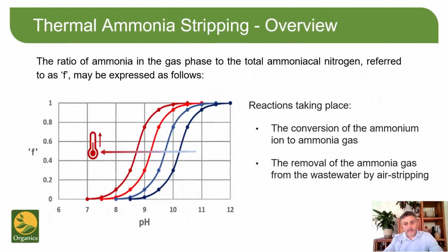The graph here indicates that as the pH increases, the ratio F, which is the propensity of the ammonia to occupy the gas phase, also increases. So the reaction of the previous slide moves to the right, or more into the gaseous region. What the graph also shows is that as temperature increases, this same propensity can be achieved at a close to neutral pH. So the shift to the right, the production of ammonia gas, is achieved with temperature alone.